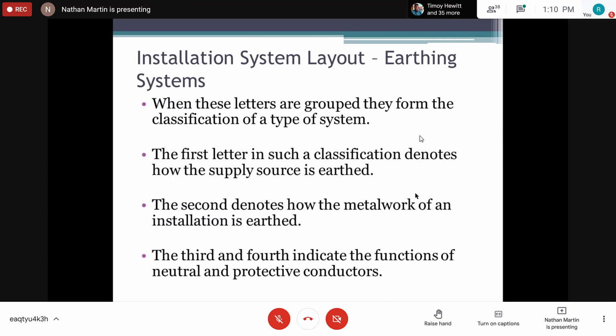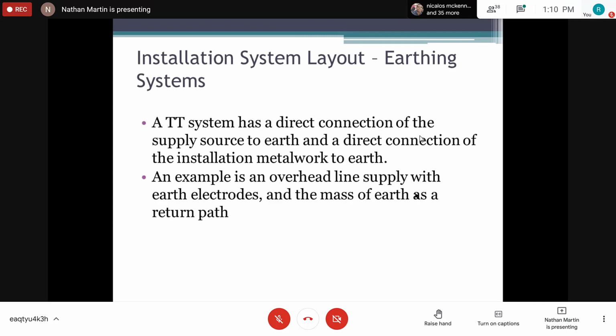The first letter of such a classification denotes how the supply source is earthed, right? So your first letter will tell you what the utility company provides, while the second letter denotes how the metalwork of an installation is earthed, right? So that's such as the metal pipes and water pipes and so forth. The third and fourth indicate the functions of the neutral and protective conductor, right? So we look at some examples of these.